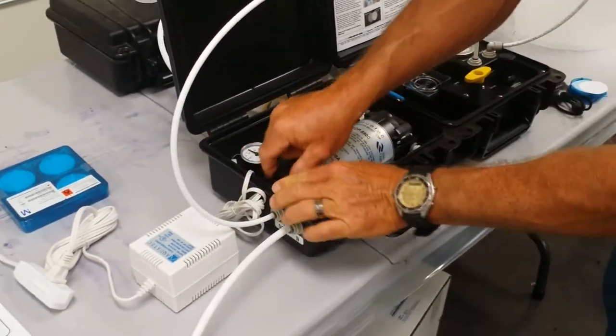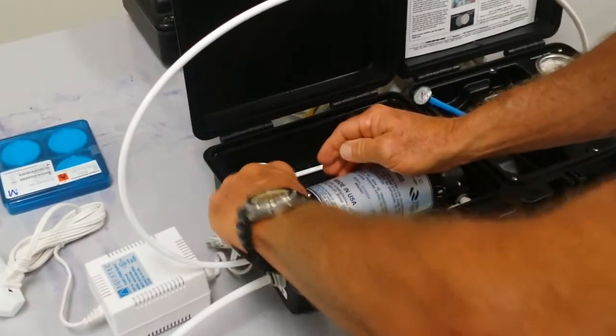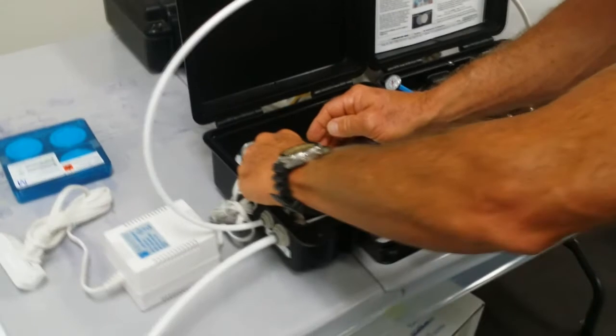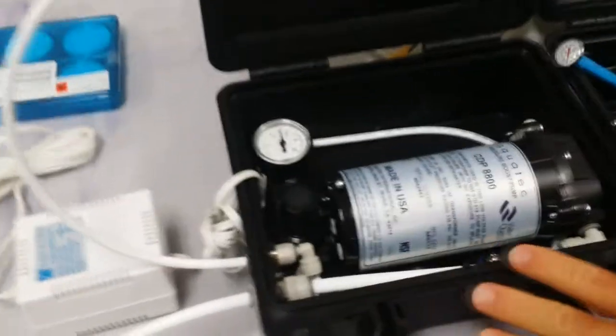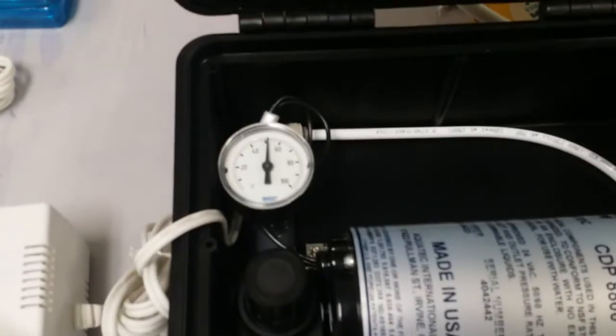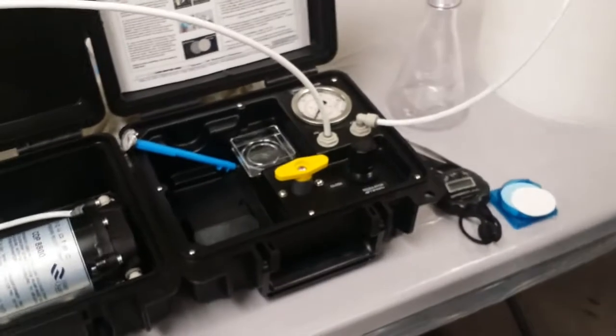We first would adjust if your system is lower or higher in pressure. What we're aiming for is 50 psi in between 40 and 60 and we're going to have a pressure drop coming over here. We want to be able to maintain 30 psi through this system.